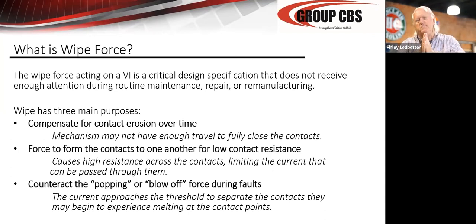People don't check that. Most shops don't check that. They just expect that it's going to do that. The way the manufacturer guarantees it does is they supply you a wear standard. So we're talking today primarily about modern breakers, vacuum breakers, not air breakers.